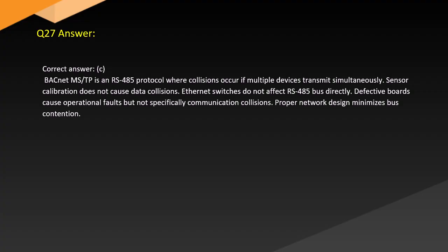Answer. Correct answer. C. BACnet MS/TP is an RS-485 protocol where collisions occur if multiple devices transmit simultaneously. Sensor calibration does not cause data collisions. Ethernet switches do not affect the RS-485 bus directly. Defective boards cause operational faults but not specifically communication collisions. Proper network design minimizes bus contention.